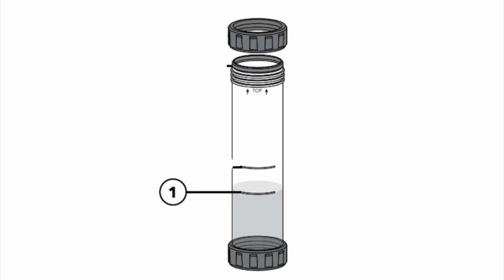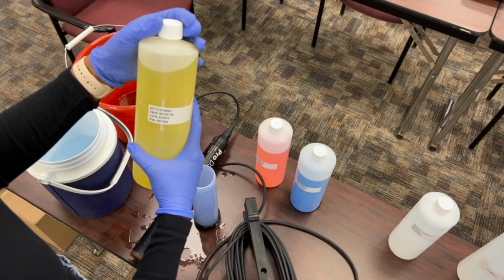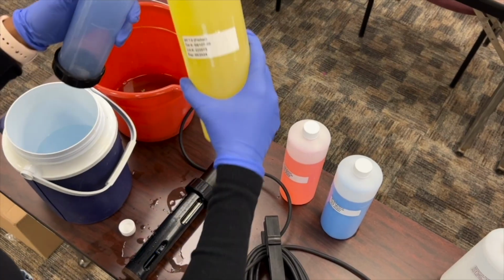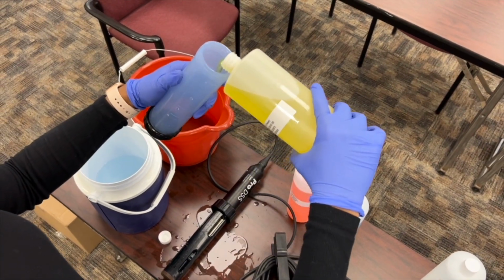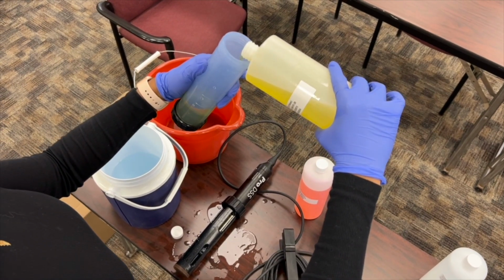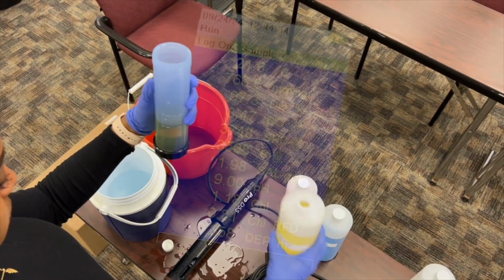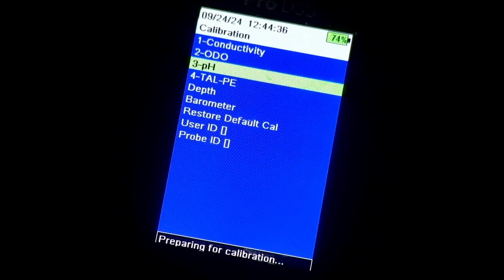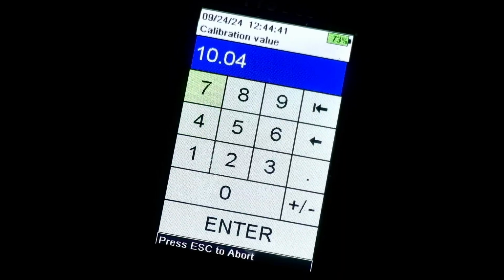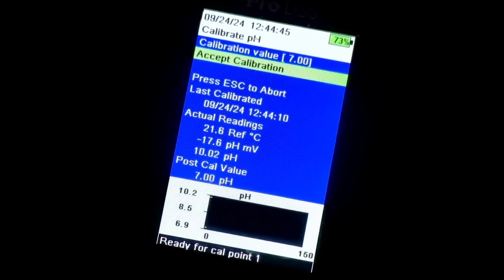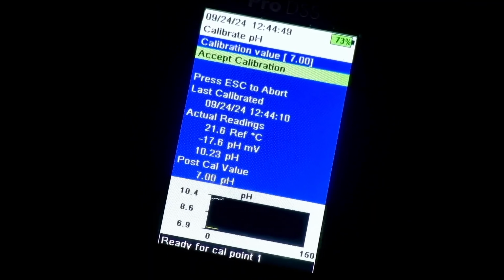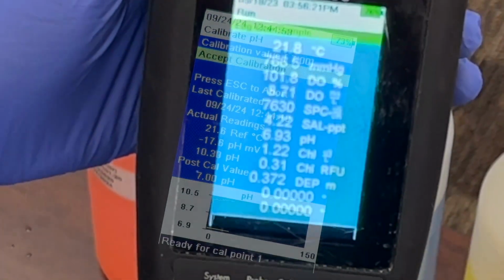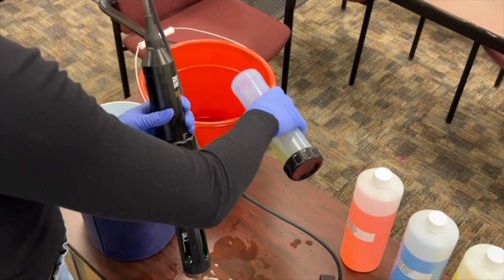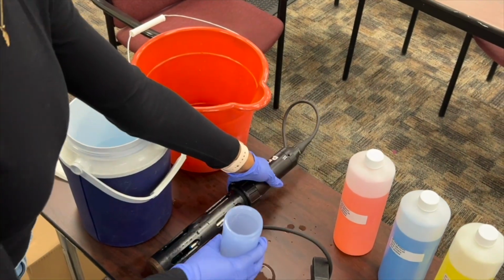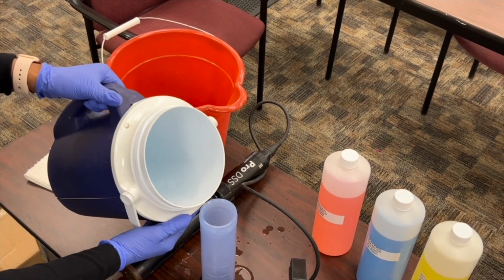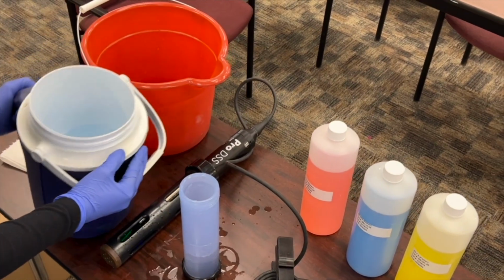Proceed to fill the cup up to the first line with the pH 7.00 buffer and then insert the sonde. On the screen, the pH value must read within 6.90 and 7.10. Record the value and temperature under post-calibration pH on the calibration sheet, and then discard the buffer. If the reading is not within the accepted range, you will need to recalibrate. If recalibration is necessary, be sure you also record the time it was performed.